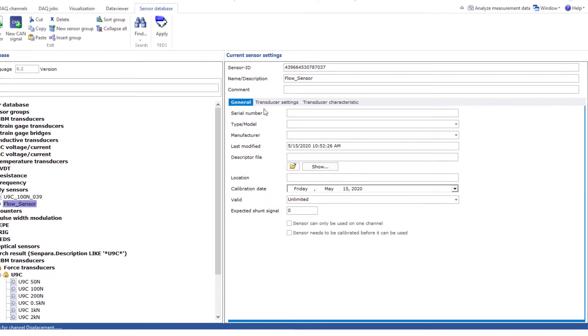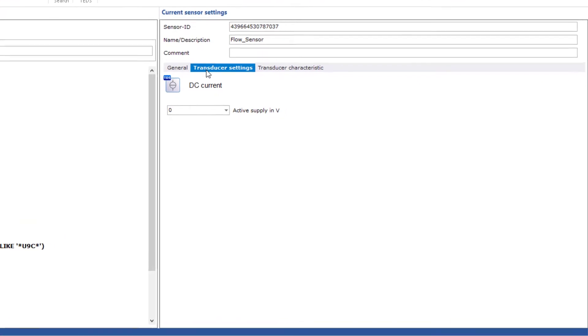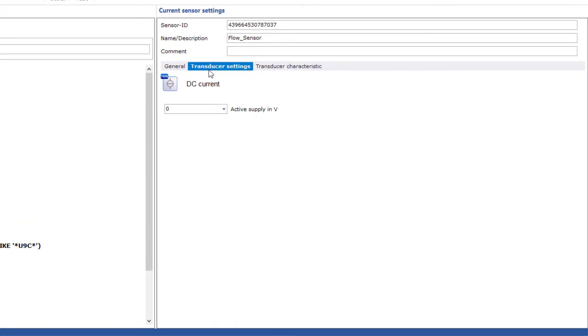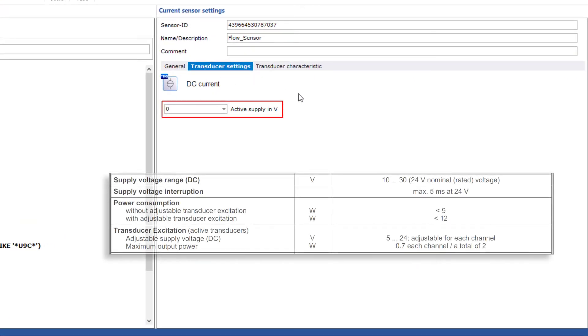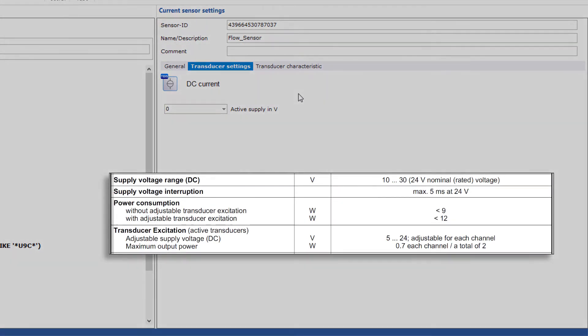If the sensor can be powered by the electronics of the Quantum X, for example, enter the supply voltage here. Most Quantum X modules can supply 0.7 watts per channel and max 2 watts per module. The possible supply voltage is between 5 volts and 24 volts, independent of the module supply.